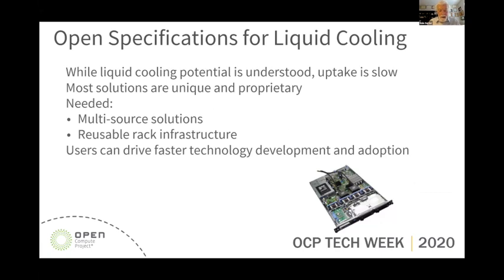While liquid cooling potential is understood, the uptake has been slow and most solutions are unique and proprietary. So what's needed is an open specification for liquid cooling, and that's what we're here, I think, talking about with OCP. What that would likely lead to are multi-source solutions and reusable racks and infrastructure.